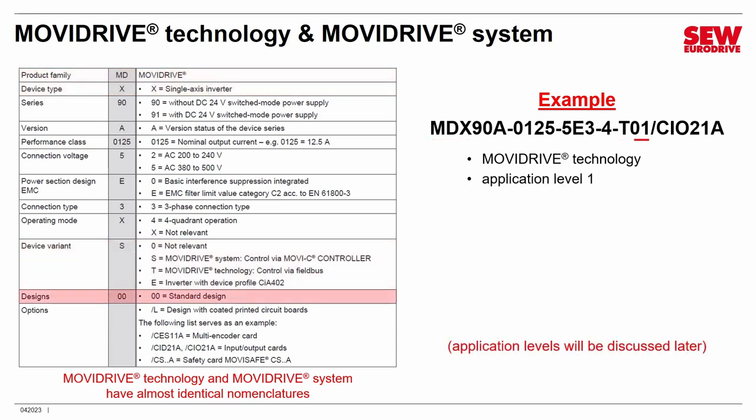Next, there is a number after the T — in this case 01. That is called the application level. MoviDrive Technologies come in three possible application levels — zero, one, or two — that determine their capabilities. An 01 is probably the most common type, meaning application level one; we're not covering the differences between levels here. Going back to the 90: that tells you there is no built-in DC 24-volt power supply, meaning you must supply 24 volts externally. That's important and very helpful to know.